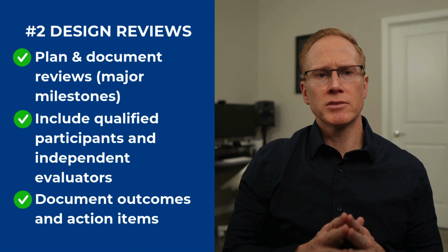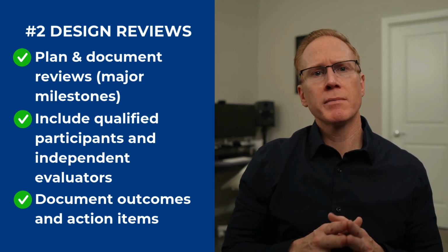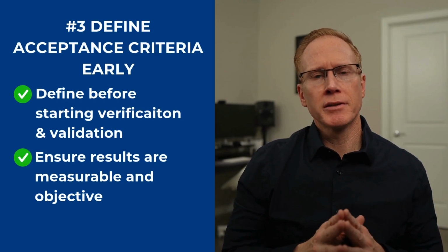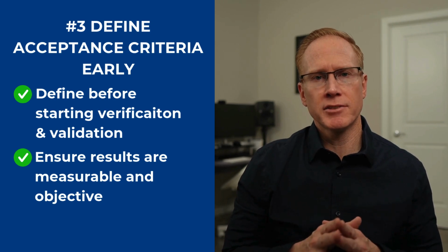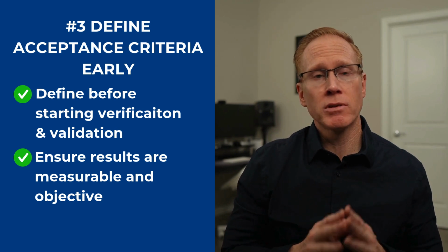Number 2, plan and document design reviews. Schedule reviews at major milestones, include qualified participants and independent evaluators, and document outcomes and action items. Number 3, define acceptance criteria early. Establish acceptance criteria before starting verification and validation. These criteria guide testing and ensure results are measurable and objective.